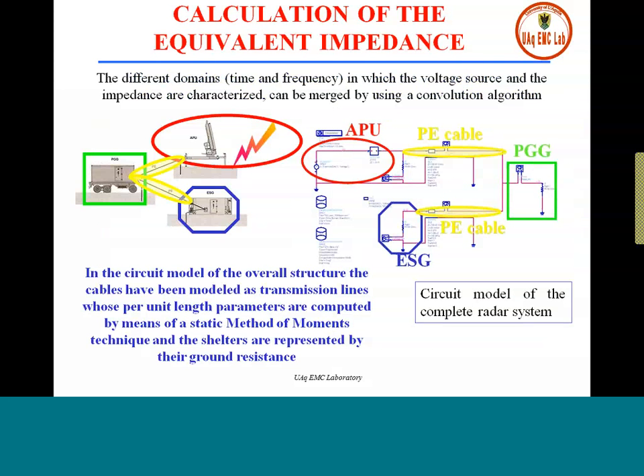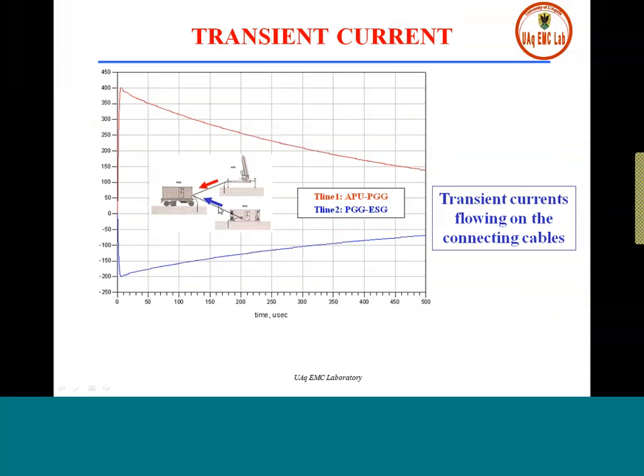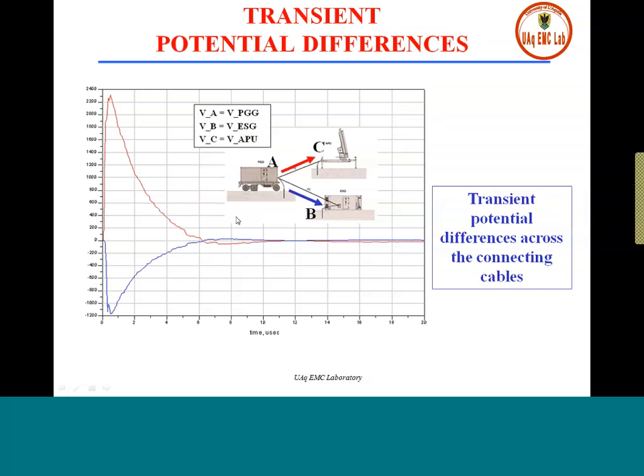Finally, we populate the ADS schematic, where the cable is modeled as a transmission line. Here you have the cable, the generator, the shelter, and the antenna. In ADS, we simulate the transient current flowing in the cables: in red the current from the antenna to the generator, and in blue the current from the shelter to the generator. We see a 400-ampere peak current. We also calculate the differential potential: in red between the generator and the antenna, in blue between the generator and the shelter — showing a 2200-volt difference of potential, which should be zero volts.